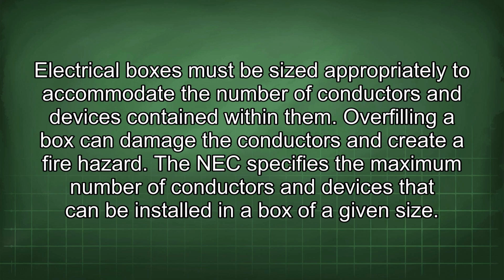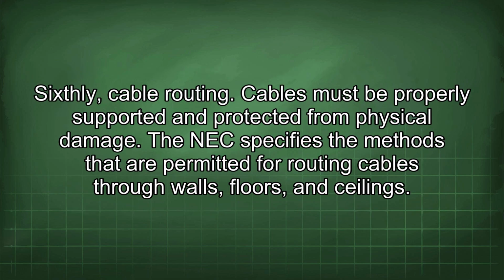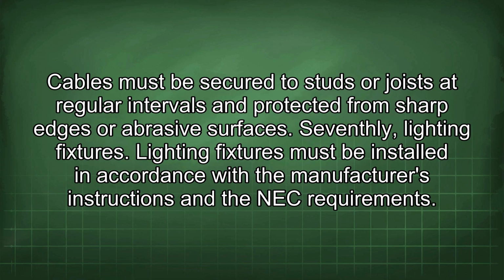The NEC specifies the maximum number of conductors and devices that can be installed in a box of a given size. Sixthly, cable routing. Cables must be properly supported and protected from physical damage. The NEC specifies the methods that are permitted for routing cables through walls, floors, and ceilings. Cables must be secured to studs or joists at regular intervals and protected from sharp edges or abrasive surfaces.